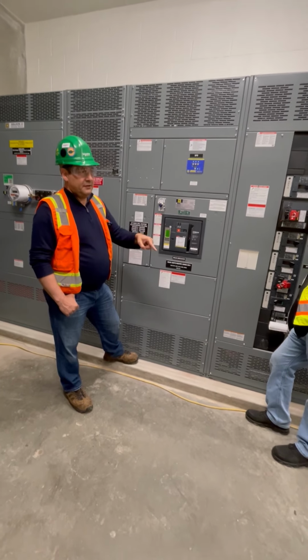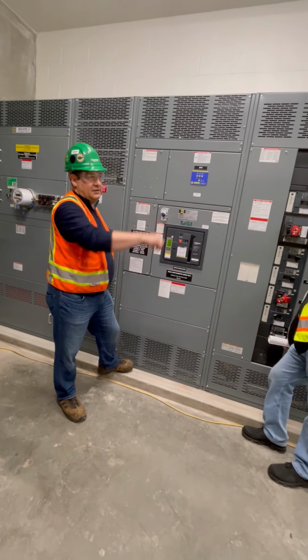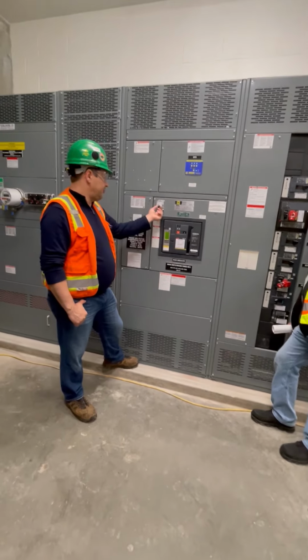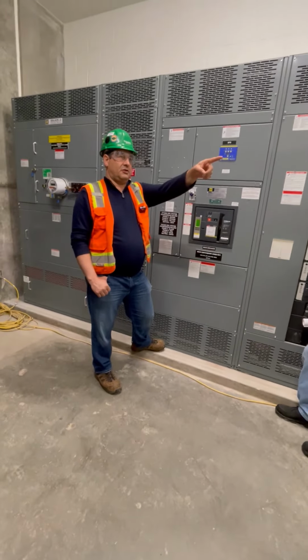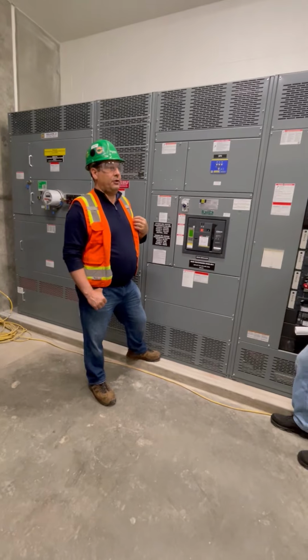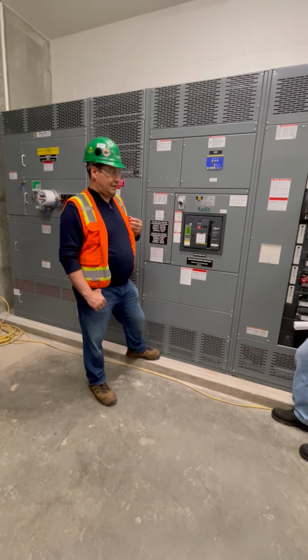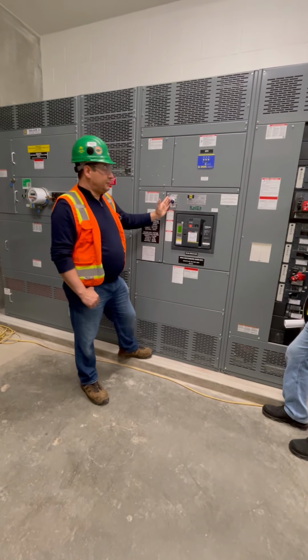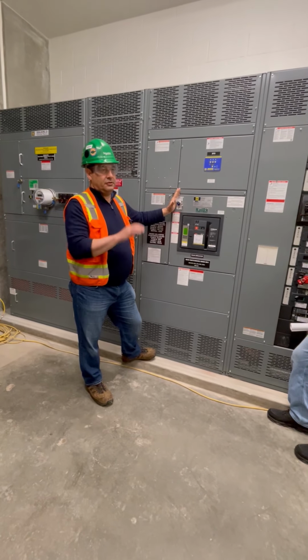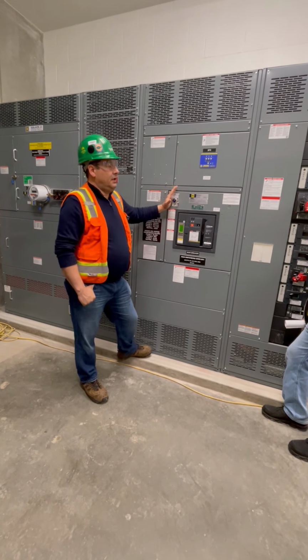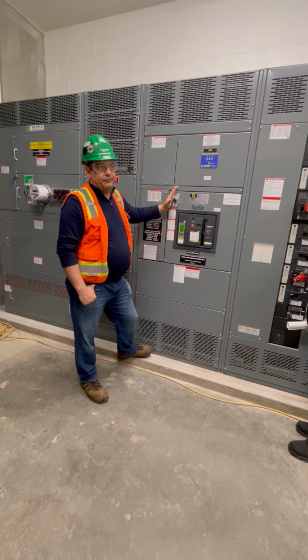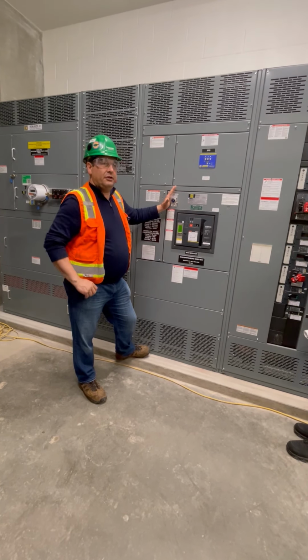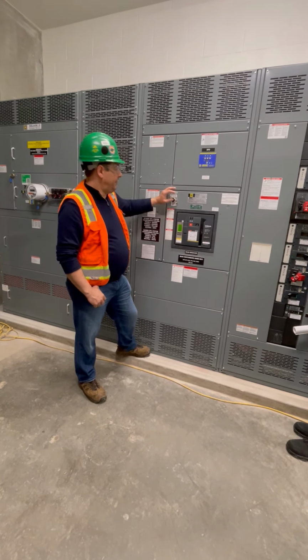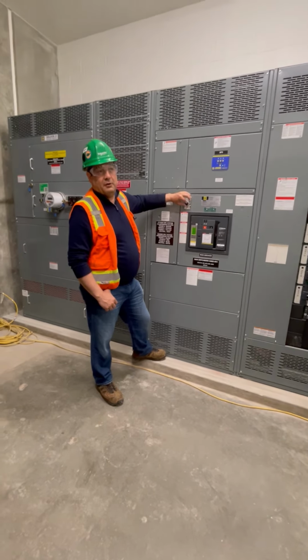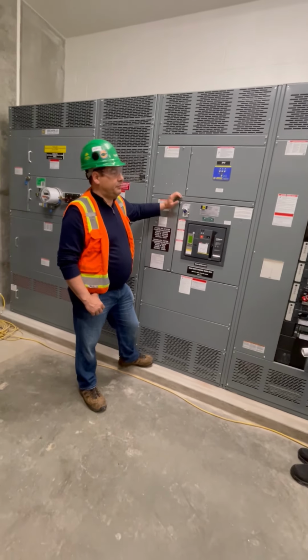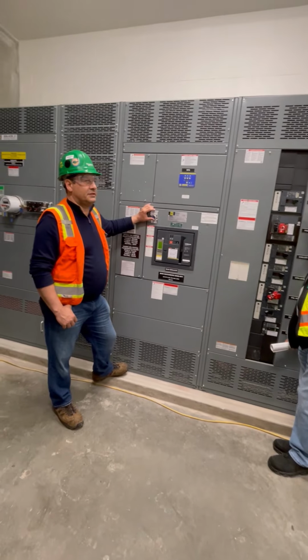Now, to some degree, if you want to get into that panel board over there, you can come over here, put this in the on position, and it reduces your arc flash at that panel. Although we don't recommend working on anything that's energized. But that's the intent of it, to reduce arc flash downstream. If for whatever reason you're looking at reducing that level, it's always recommended that when you're done with the work and you don't need it, you put it back in the off position, and it needs to operate in the off position.